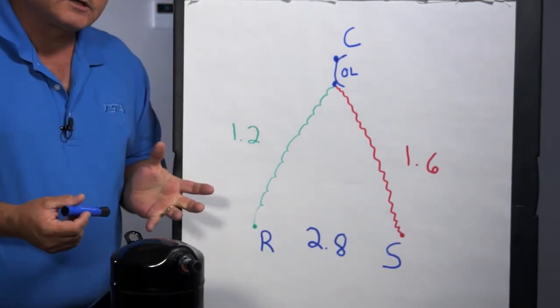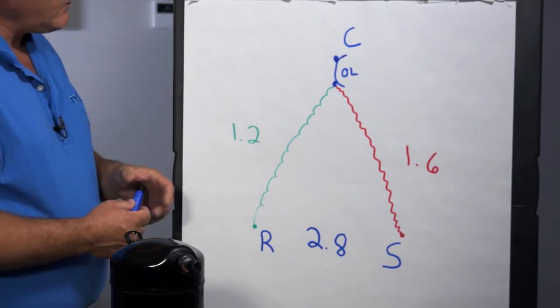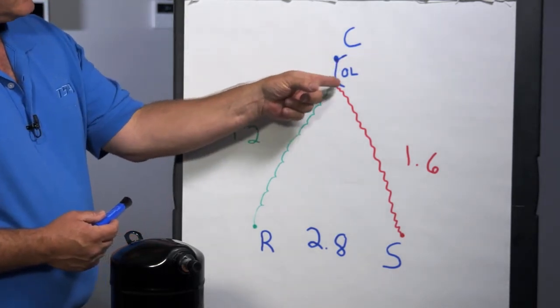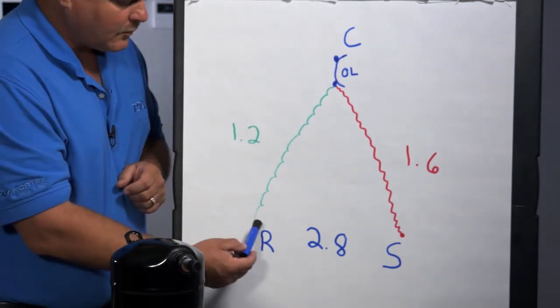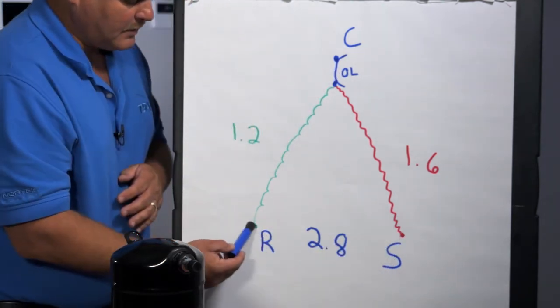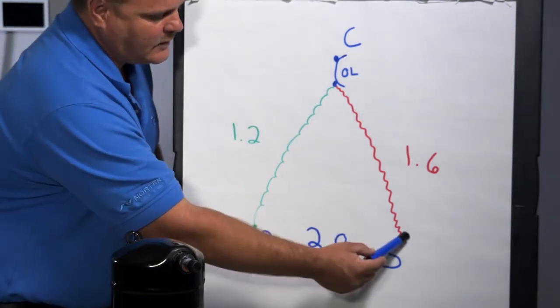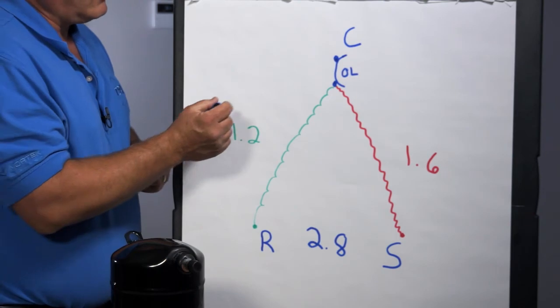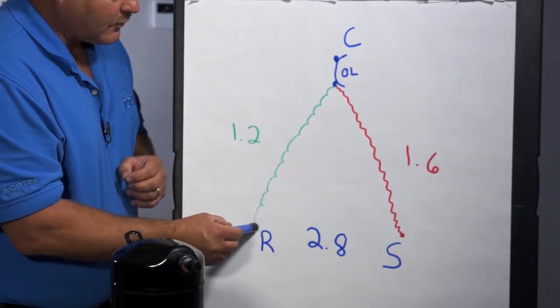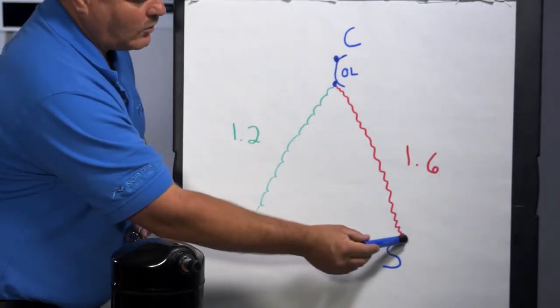So then the other one is open overload. If I have an open overload, and that's what I got drawn in the picture here, if that overload is open, you will get a reading between run and start because you've got an electrical path through the windings from run to start. If the overload is open, you won't get a reading from run to common or start to common.